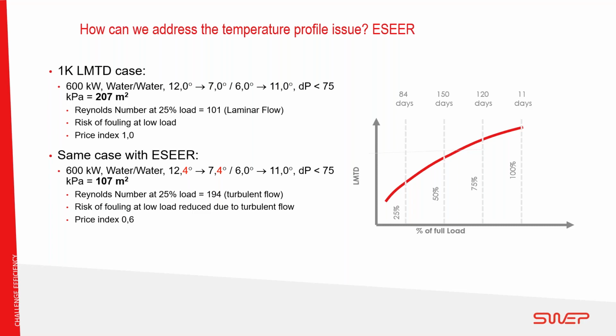The example here shows the application of the ESEER profile, which reduces the heat transfer area from 207 to 107 meters squared. The 207 meters squared selection provides turbulent flow down to around 60% of the peak load, whilst the 107 meters squared selection can provide turbulent conditions down to 25% of the peak load. There's also a reduction in capital costs of around 40%. Yet the increase in the LMTD is only 0.4 degrees at the peak load. The original 1 degree LMTD that was specified would still be achieved most of the time.